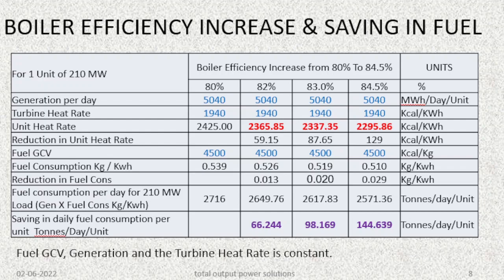If the fuel GCV is constant at 4500 kcal/kg, the fuel consumption rate would decrease from 0.539 to 0.510 kg/kWh. For 210 MW, the maximum saving in daily fuel consumption per unit — from 80% to 84.5% boiler efficiency — would be 144.639 tons per day per unit. The fuel GCV, generation, and turbine heat rate are assumed constant.